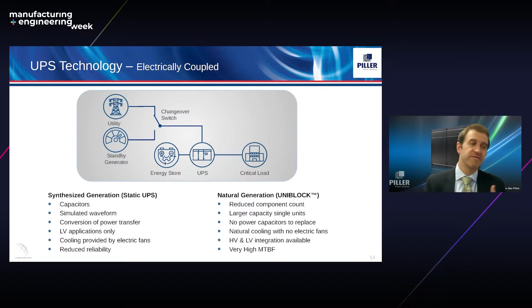They're very well suited to support very difficult mechanical type loads, whether high power devices with inrush, or perhaps drives run off variable speed drives, which impose harmonics to the supply. But they can just as easily support IT equipment, or any combination of the different types of loads you might find in a facility.